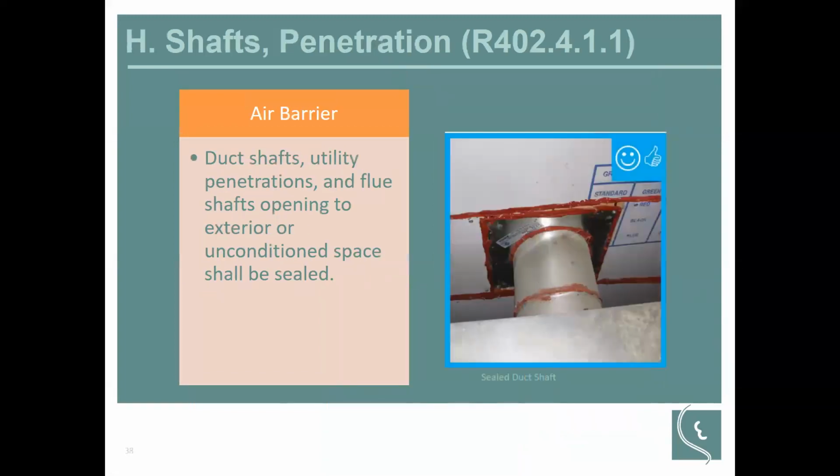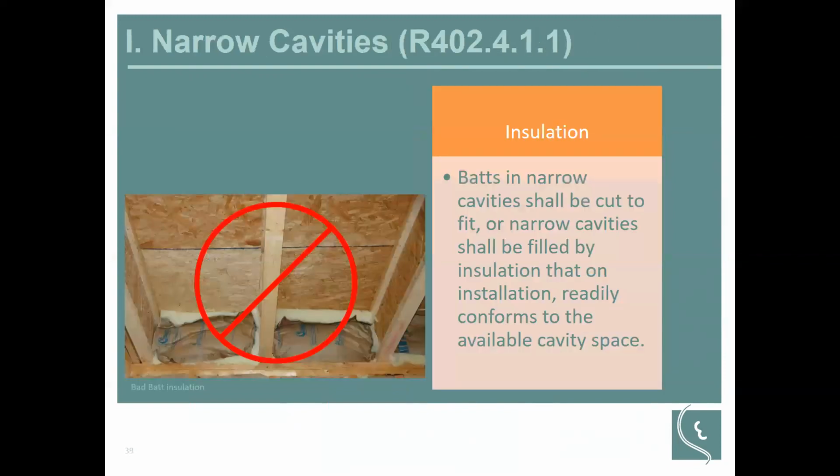Looking at shafts and penetrations, this is a look at a rear vented fireplace. And so you can see they've gone ahead and fire caulked all the joints around it, and even gone so far as caulking the joints in the flue there as well, making sure that any penetrations again are sealed.